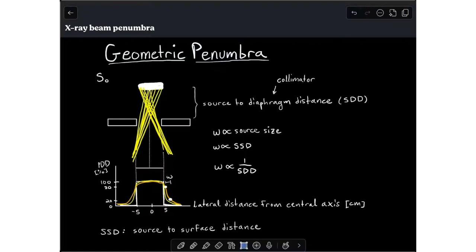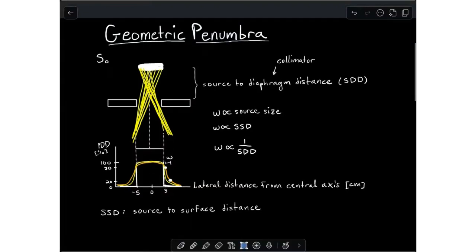So in addition to the effects of various distances and angles, a real problem we have to consider with photon beams is that their interactions in matter are probabilistic, meaning that some fraction of the intensity of an incident beam, however small, will inevitably, in all likelihood, leak out through your shielding material, including the collimators, and pass through regions where you would really prefer it didn't, such as the outskirts of your field.